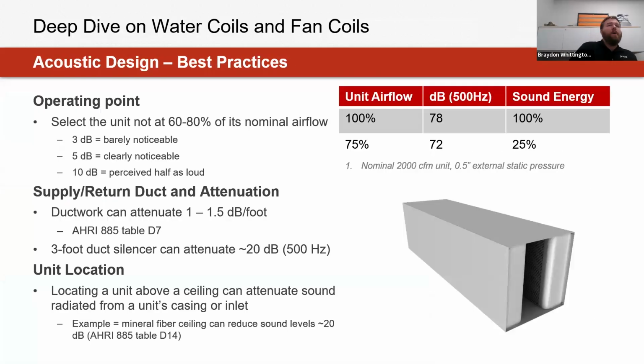So different ways to try to design around, I would say, fan coils and blower coils for this equipment is selecting it around that 60 to 80% of its nominal flow range for a fan coil or a blower coil. The reason for that being is that that's going to save a high level amount of noise that's really going to be emitted from the product than trying to run it at full maximum of what used to be more typical of what you would see for a PSC motor, especially when trying to yield as much energy savings as what you could get from that motor itself. But commonly, what we recommend for these is actually going to be selecting around 70% of its flow just to yield more peace of mind in terms of what performance is going to be coming from it.